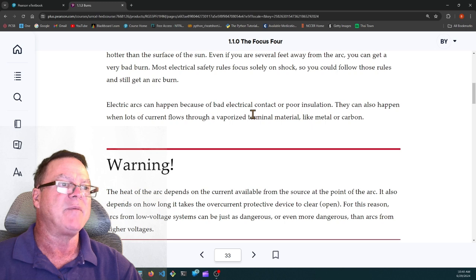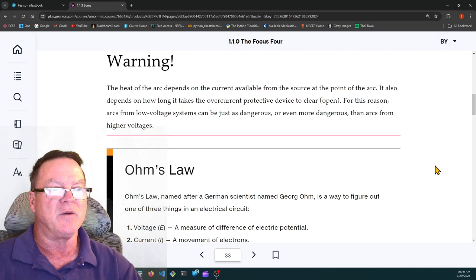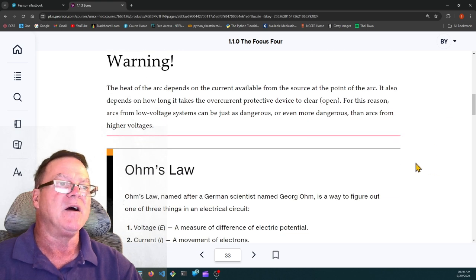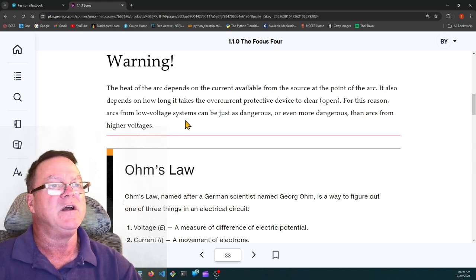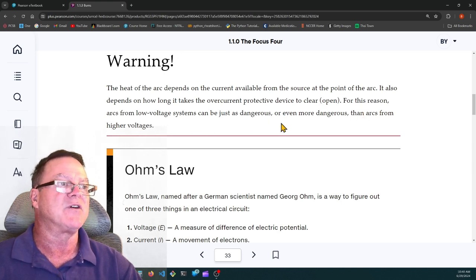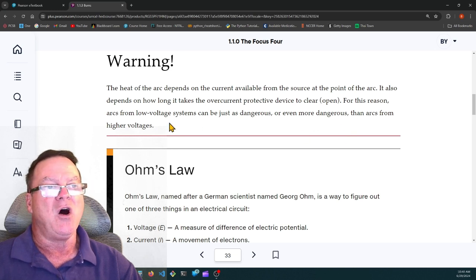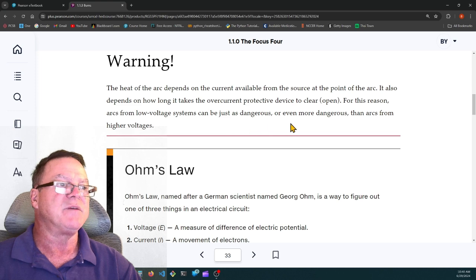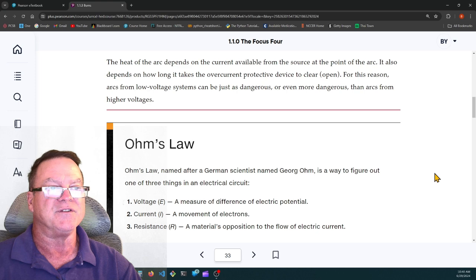Electric arcs can happen because of bad electrical contact or poor insulation. They can also happen when lots of current flows through a vaporized terminal material like metal or carbon. The heat of the arc depends on the current available from the source at the point of the arc. It also depends on how long it takes the overcurrent protective device to clear or open. For this reason, arcs from low voltage systems can be just as dangerous or even more dangerous than arcs from higher voltage systems.